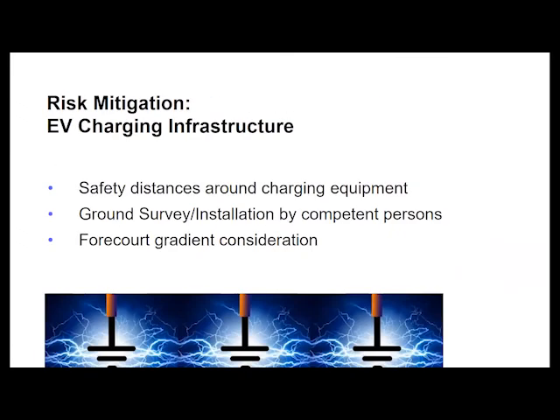The next slide deals with risk mitigation and how to try and mitigate against them from a petroleum inspector's point of view. The first thing to establish, as with petroleum hazardous zones, is safety distances. The electrical energy within charging equipment has the potential to cause a spark, therefore no part of the installation can be within a hazardous zone. This includes the length of an electric vehicle, plus the length of the charging cable at full extension from the cabinet. This aims to mitigate against the risk of a spark reaching the hazardous zones. Also, charging cables should be tethered to the charging cabinet, thereby removing the option of custom-made cables of unknown lengths, unknown quality, unknown condition being attached.